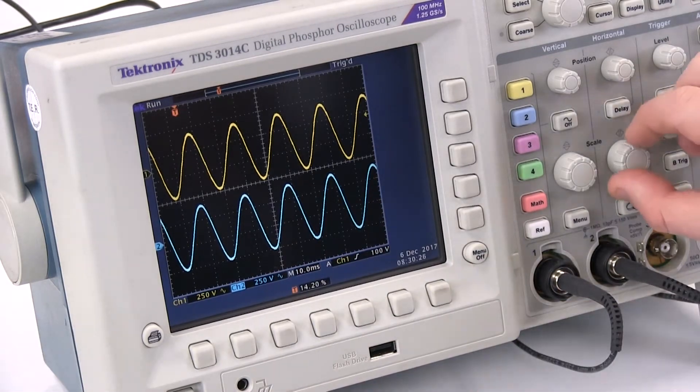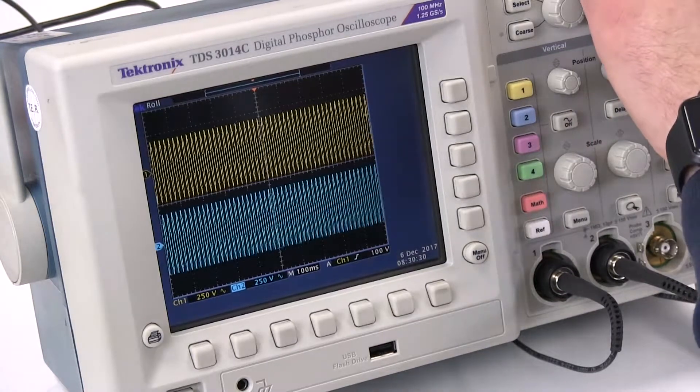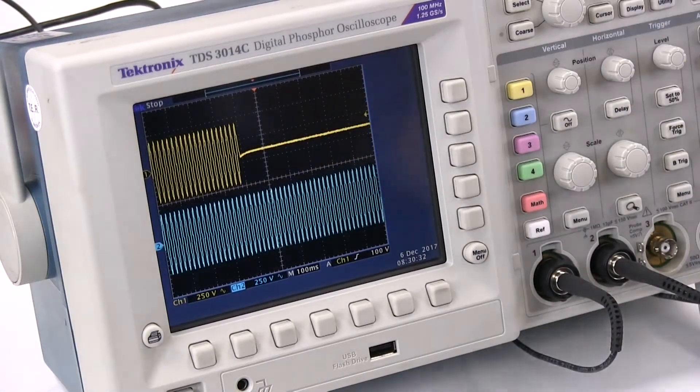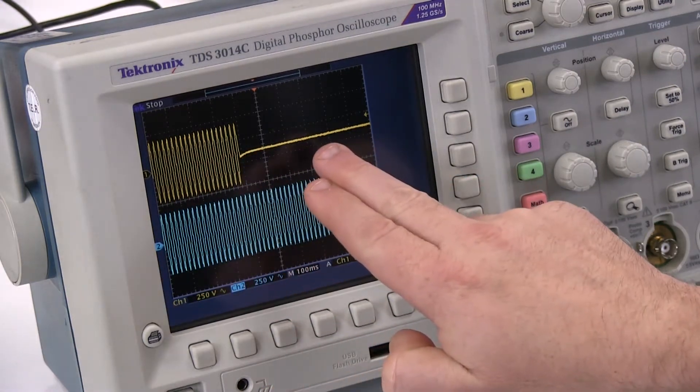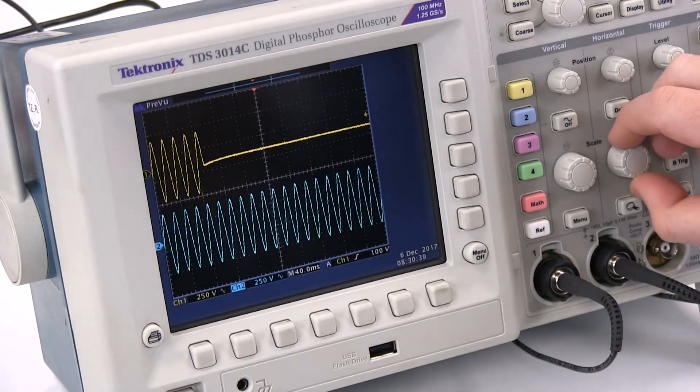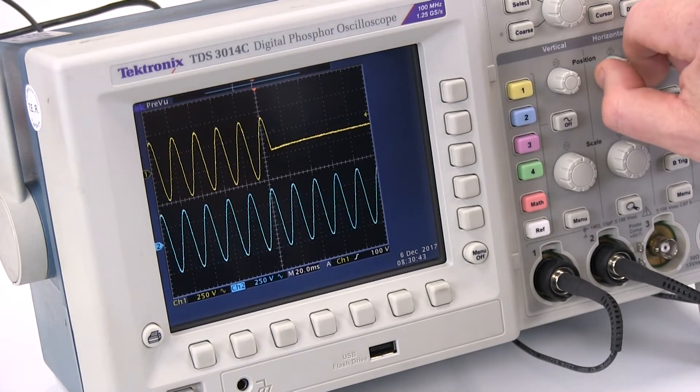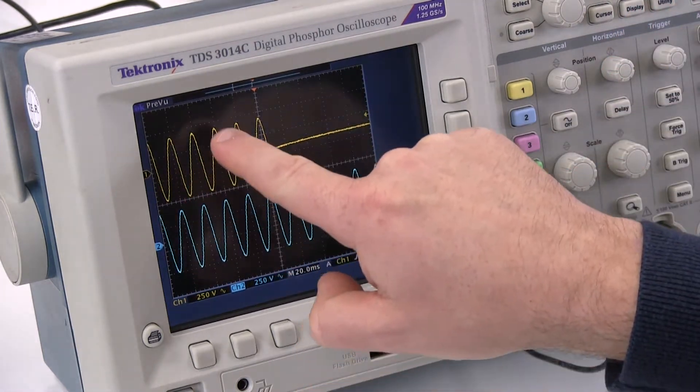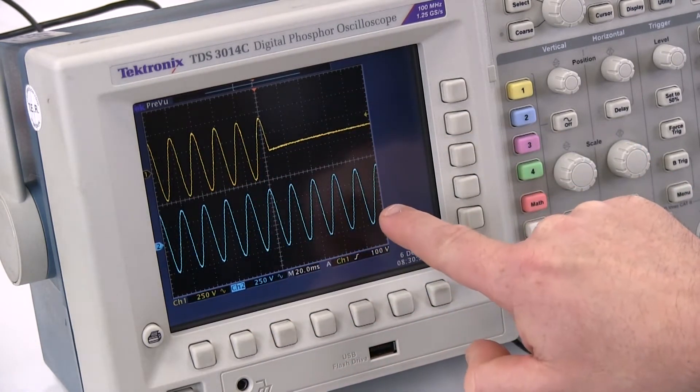Now if I slow the trace down and then fail the main supply to the UPS, I can stop the trace and effectively capture the moment when the main supply fails. If I zoom into that moment, you can see that even though the main supply has failed, the output from the UPS system remains completely unaffected.